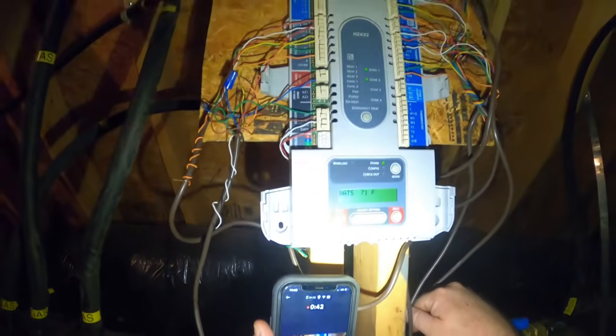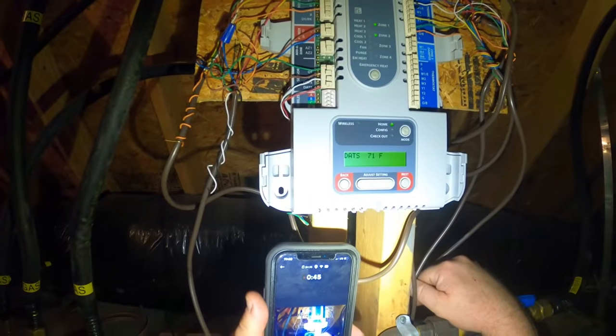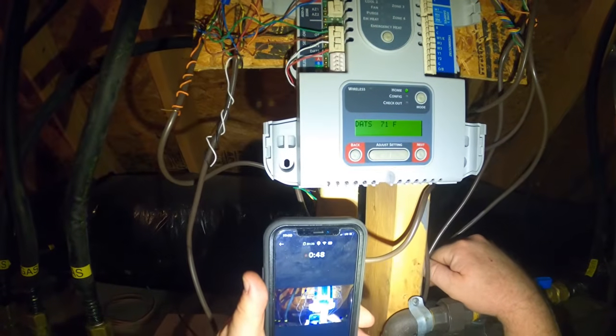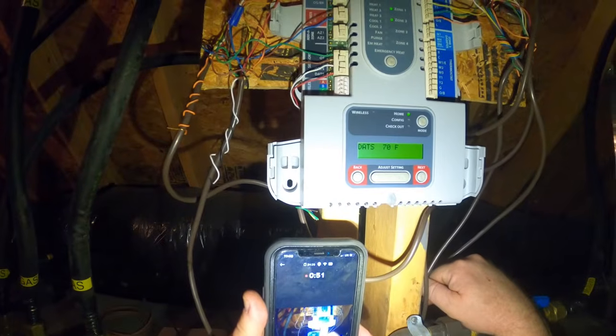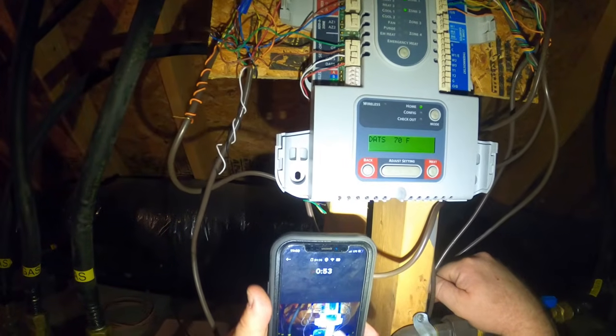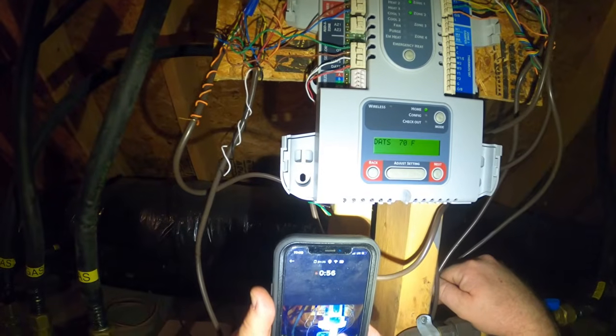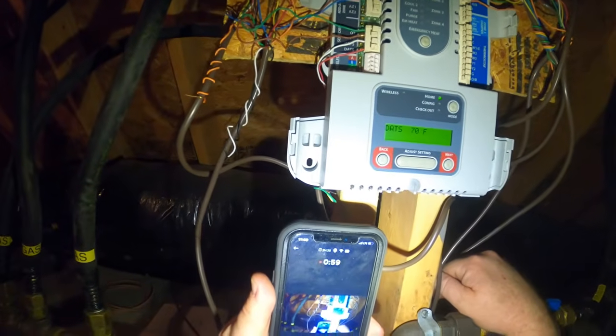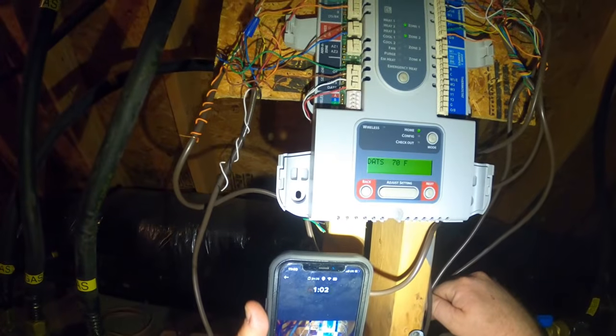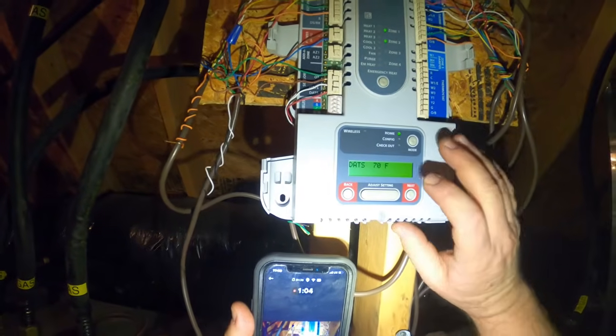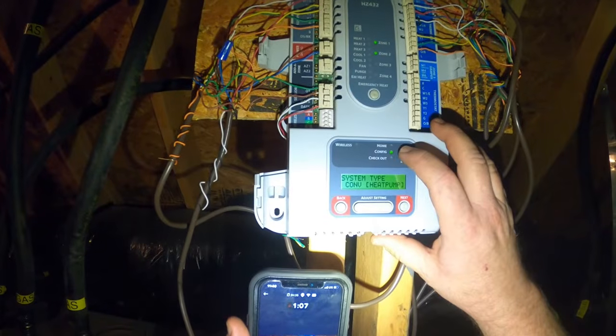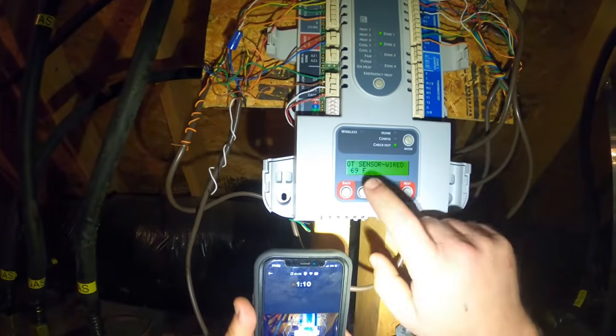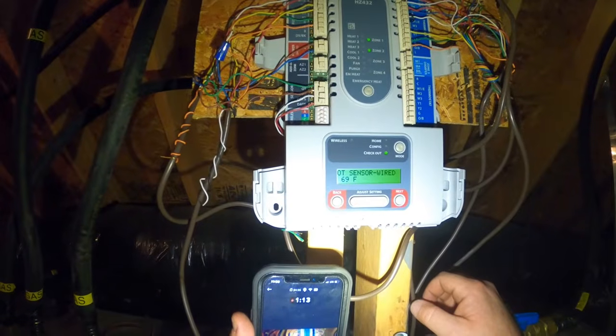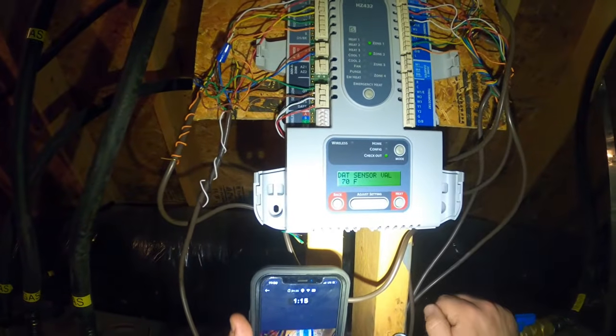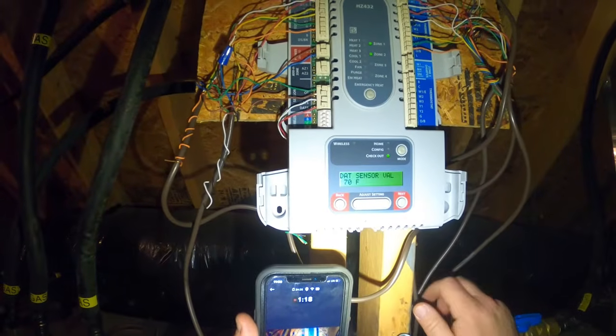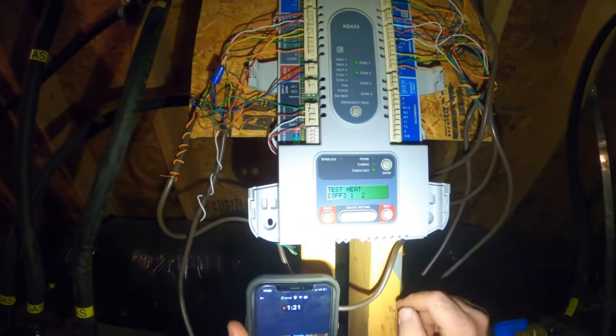And we're going to go through our test modes real quick with the zone board and check each thing one at a time. It'll cycle on the heat pump, the blower, cycle on the furnace. Waiting for the time to play on that Carrier furnace. You gotta love it. But I'm gonna go ahead and go into our configuration. We've already got everything set up, our checkout mode. So right there, like I said, it's telling us our outdoor temperature is 69 degrees. It's telling us our supply temperature is 70 degrees from our sensor. So now we're going to do our test. Heat 1.